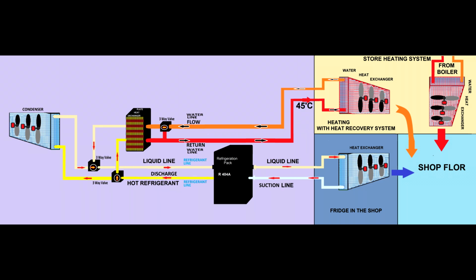And honestly, if your shop gets very cold, about 5 degrees, let's put it this way, then you will not have any duty on your refrigeration equipment, because there's nothing to warm up the product. So the refrigeration equipment will work very relaxed, and there will not be energy to be recovered, and then you will freeze in your store. So it is a very absurd and weird idea of believing that a heat recovery system will heat up your store. I worked for Marks and Spencer in Yorkshire, Sheffield, and I found only a heat recovery system fitted there, and the store would expect a wonderful, miraculous temperature, and that was not possible. That was a very bad mistake.